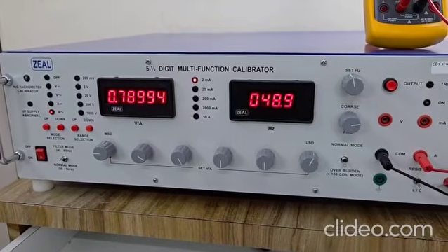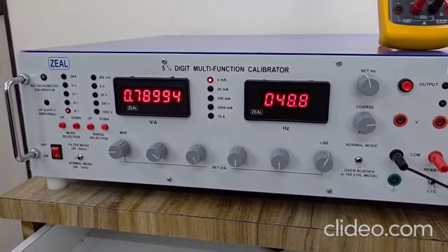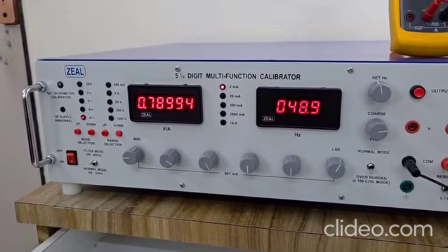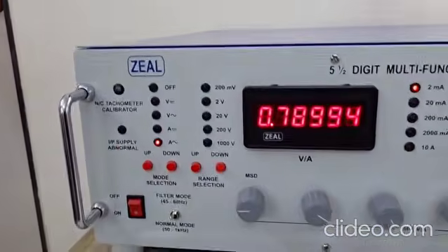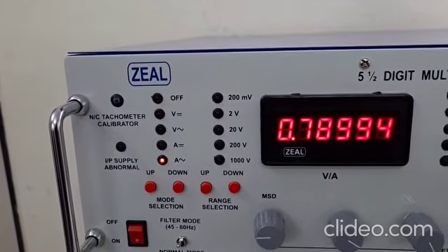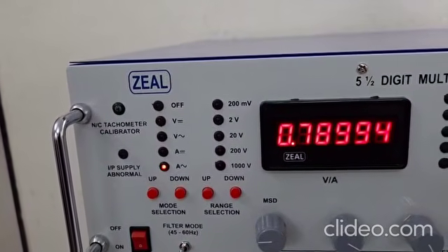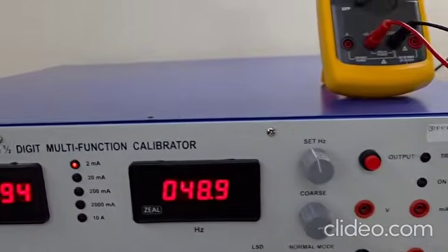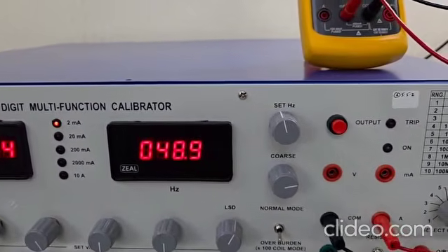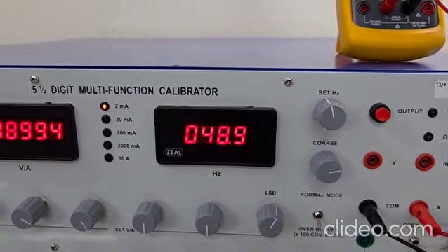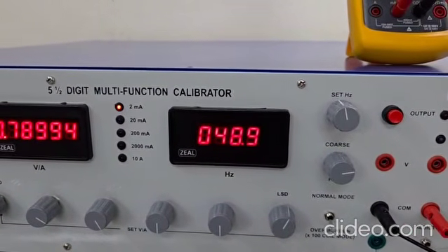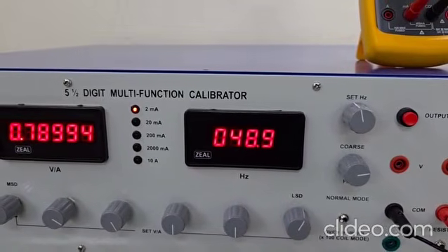Now using this multifunction calibrator, I will show how to calibrate a non-contact type tachometer. First you will have to select any of the AC ranges, and using the coarse and fine potentiometer you can set the frequency. So basically any frequency multiplied by 60 will be RPM.